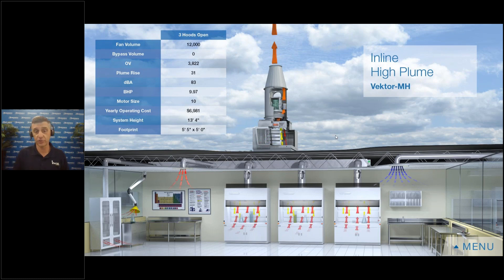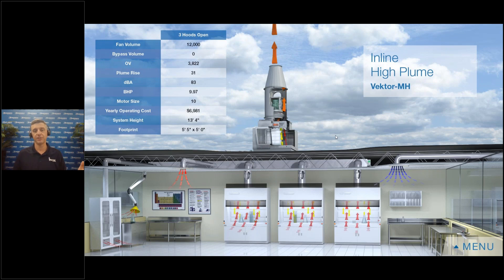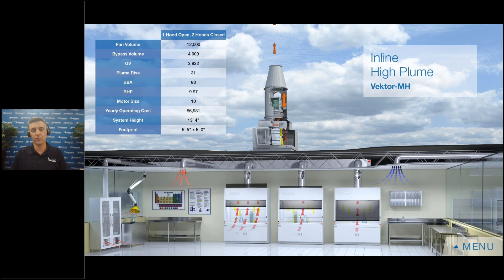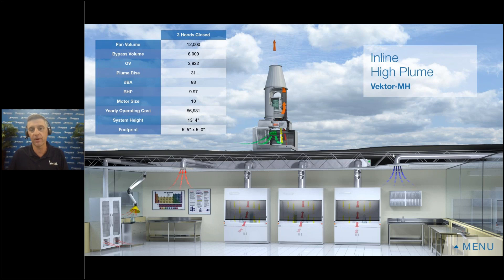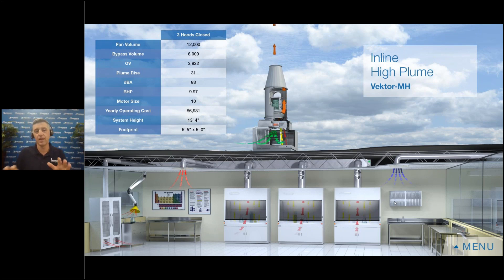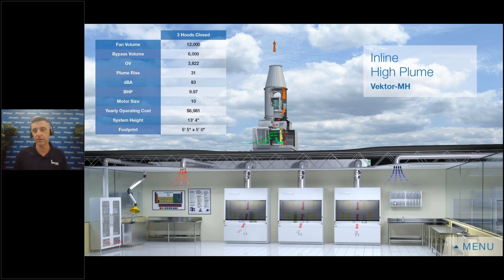When I open the sashes I need more containment at the hood level, so I need enough duct pressure. That modulating damper starts to close until I'm back to 100% utilization. With a lot of controls and moving parts, it's ultimately about life safety — but we want the energy benefits too. When researchers close their sashes on nights and weekends, we limit the amount of air coming in, reducing the amount of air that has to be humidified or cooled, and the overall energy consumption of that lab decreases.